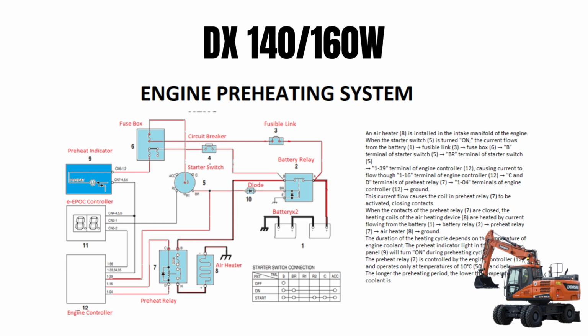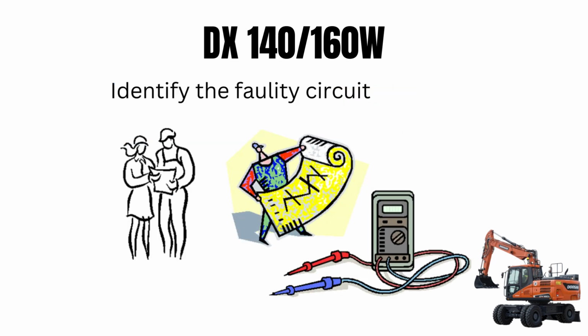So once this preheating time starts, this preheat relay is also controlled by the engine controller, and the light in the panel shows the preheating cycle. If this light displays in the panel, then the EPAS and machine controller are connected, and these will display the light. Once the preheating cycle time is finished, this light will automatically go off.